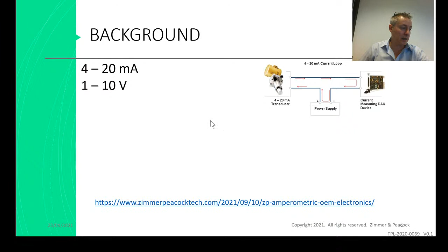So when you ask about 4 to 20 milliamp sensors or signals, what you often have in that system is the transducer itself, plus a power supply - because 4 to 20 milliamps is actually quite a lot of power, especially in this age of portability and low power. And you need a DAQ, a data acquisition card. Thinking about this question, which I'll start answering in a minute, I realized that this little board we have is actually a DAQ card, a data acquisition card.